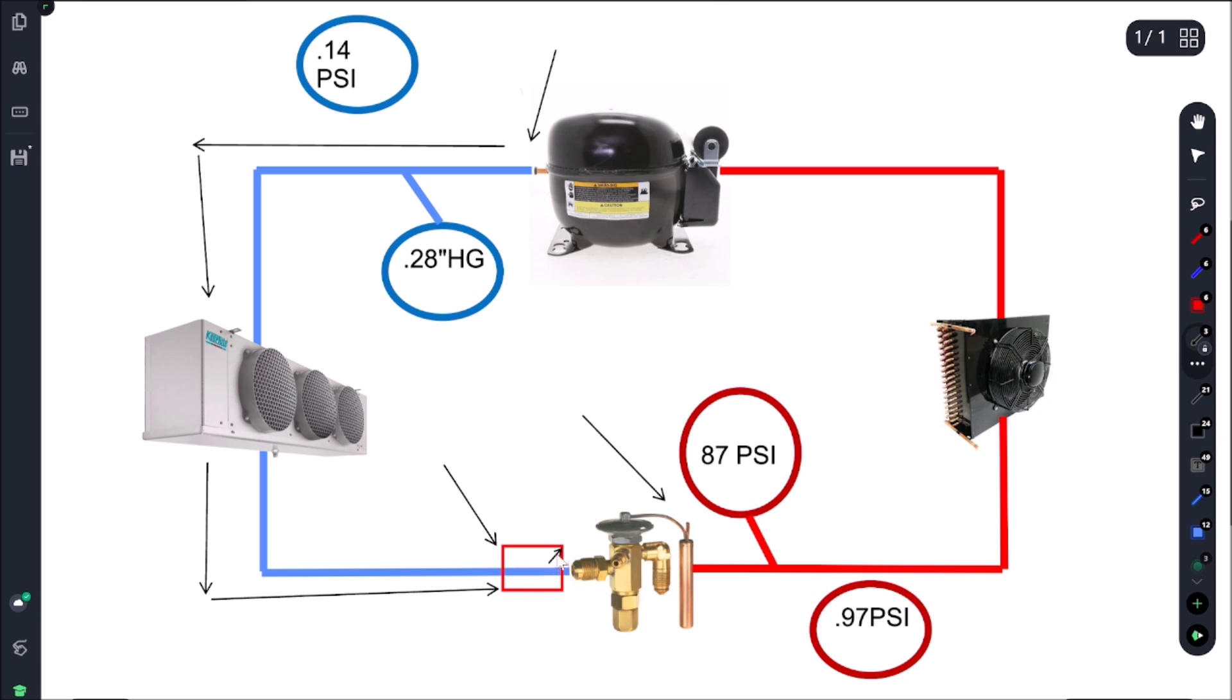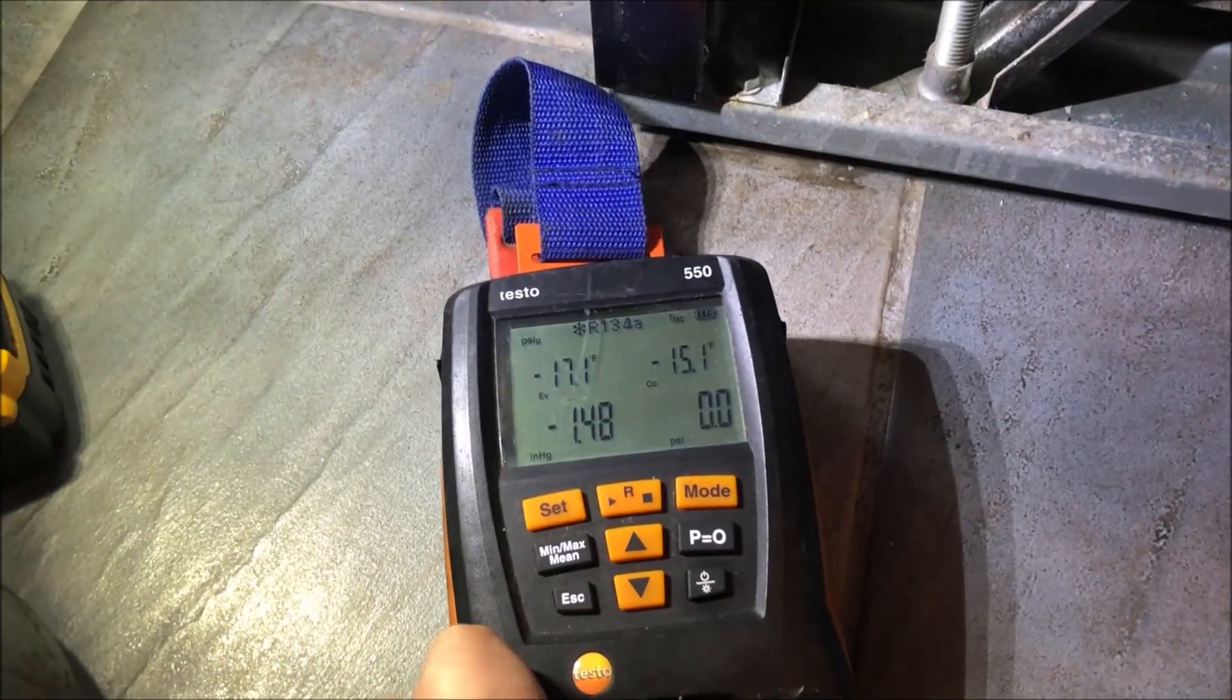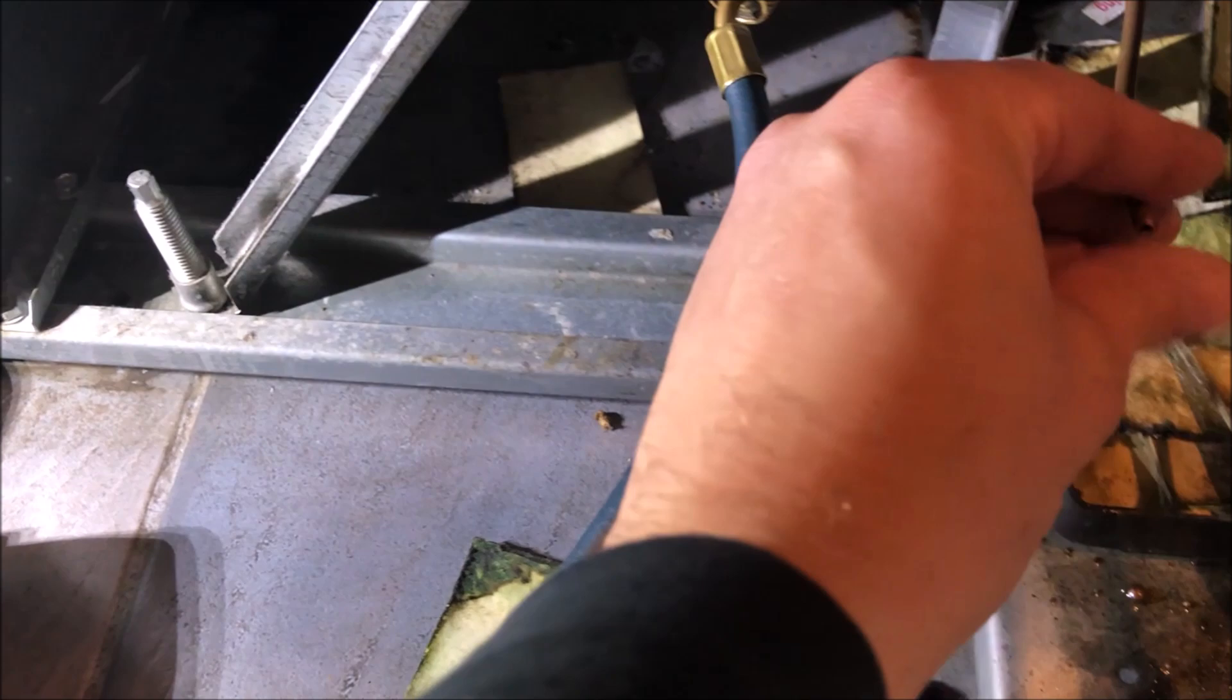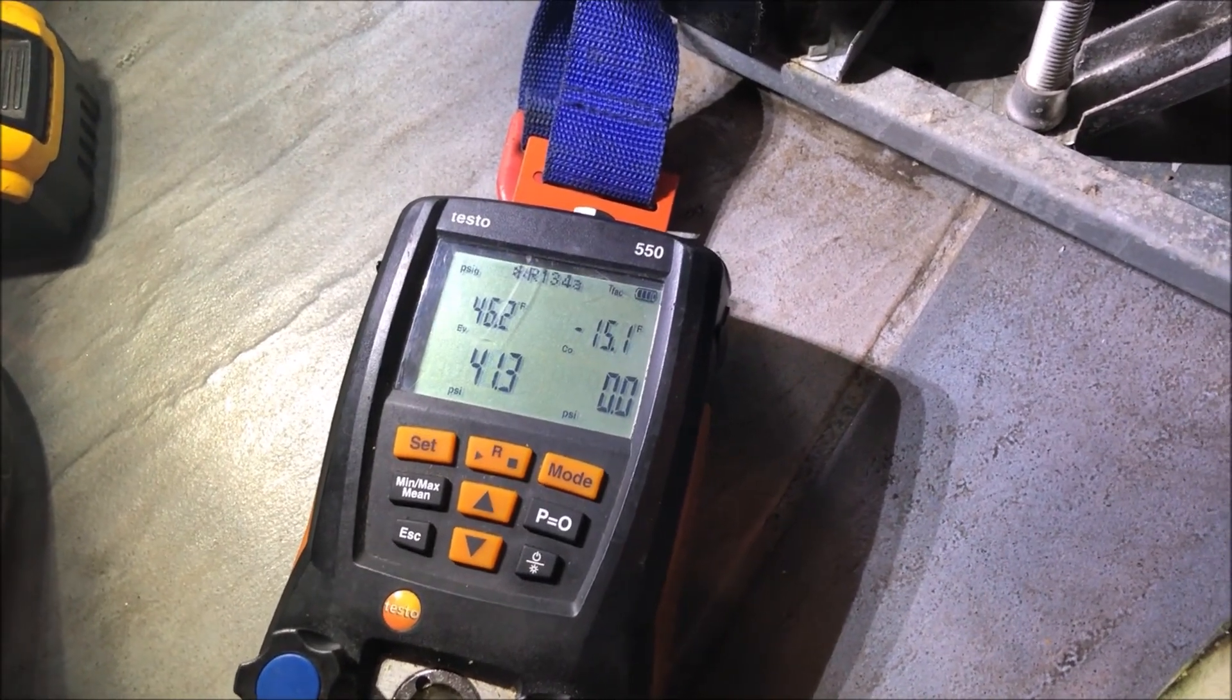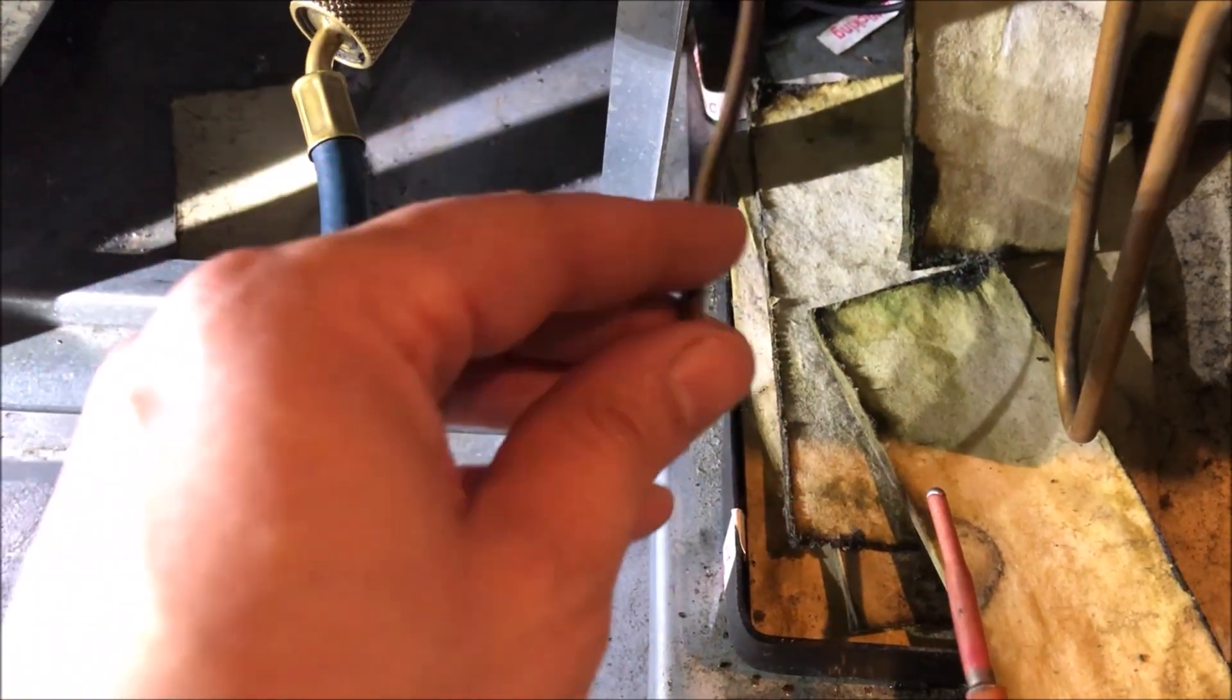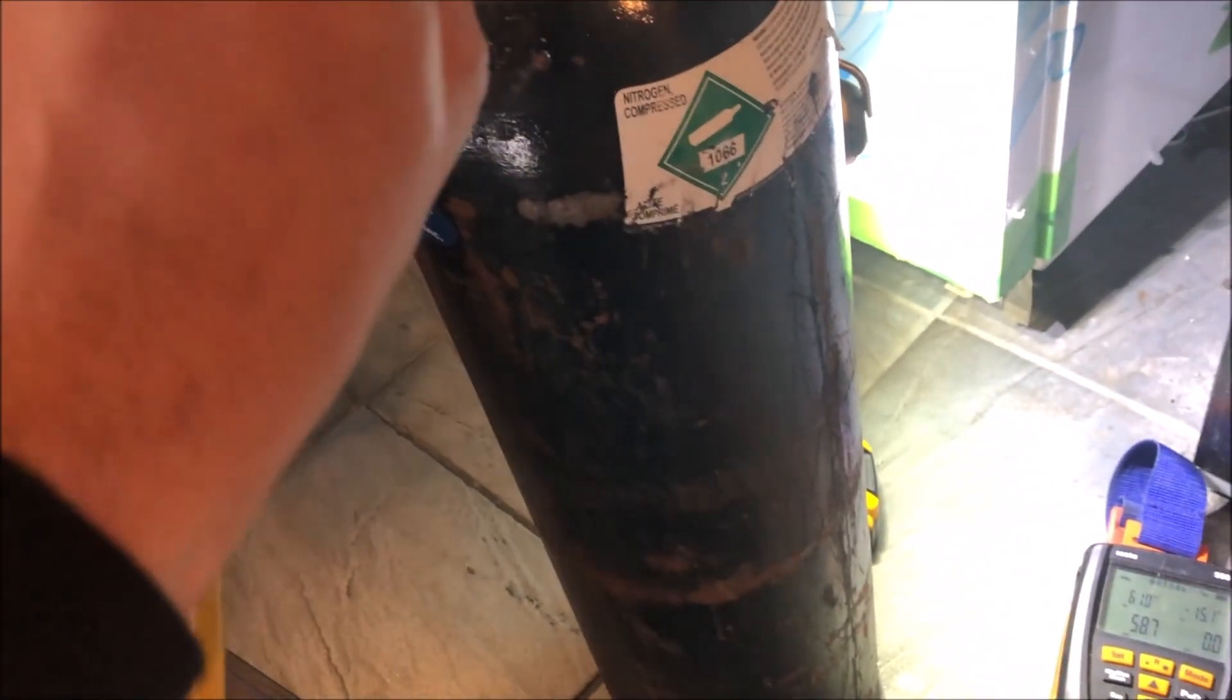All right, so we got our nitrogen bottle set up. As you can see here, we're set up on that compressor. Here's the end of our cap tube, it's open. At the other end of the filter dryer, the outlet of the filter dryer is closed. So we're going to keep pushing nitrogen through until we can hear it. So right now we got about 36 pounds of pressure, it's coming through but it's barely coming through. Let me just block the end here and there we go, now we got really good flow. Whatever was plugged in there is unblocked.